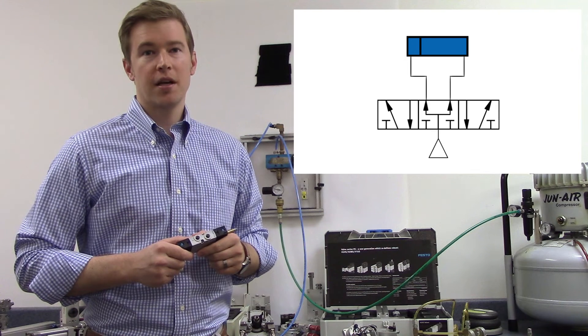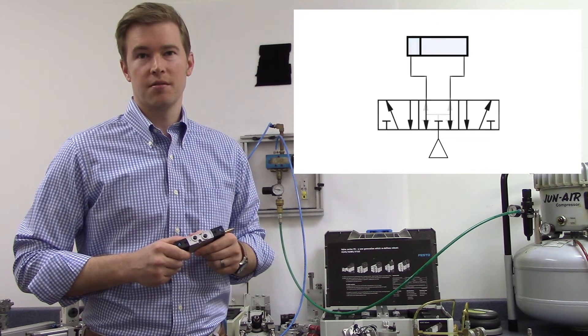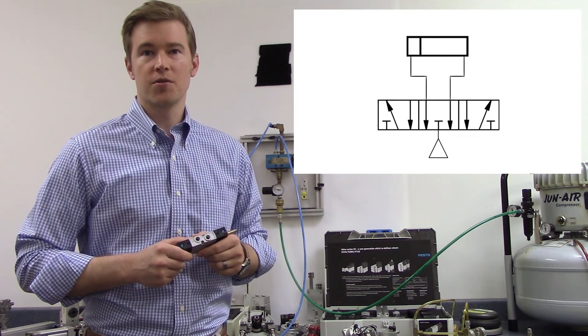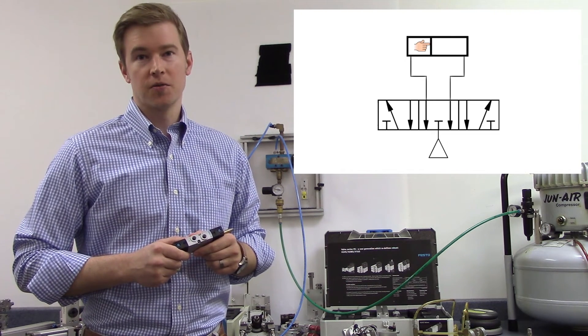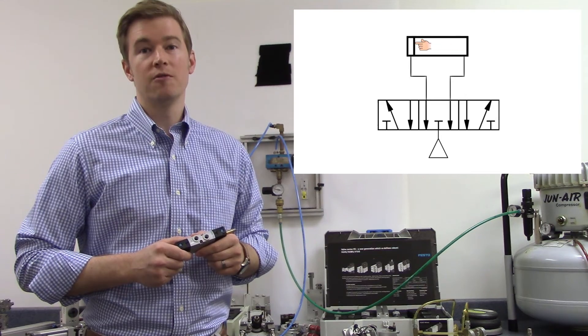Yet another case is the middle position exhausted, where the working lines and the two exhaust ports are left open, so all air is purged from the actuator. This is useful in cases where the actuator needs to be moved by hand.